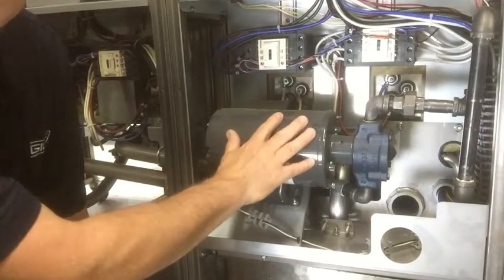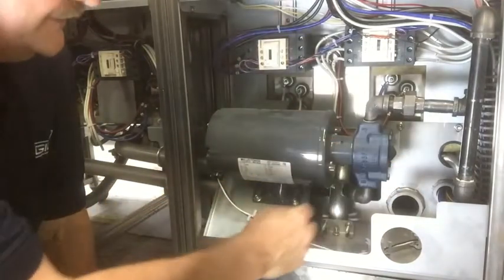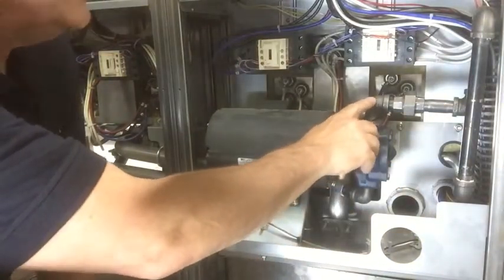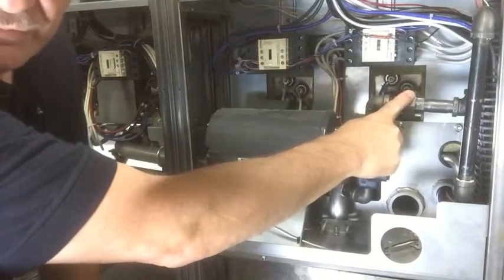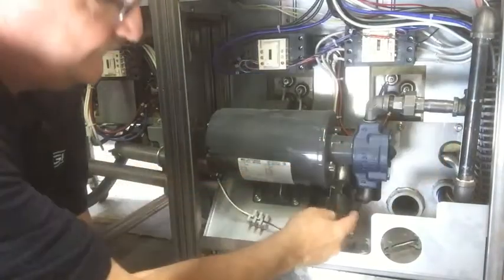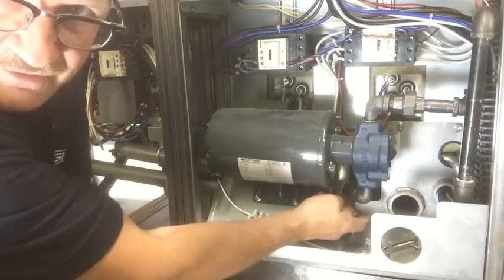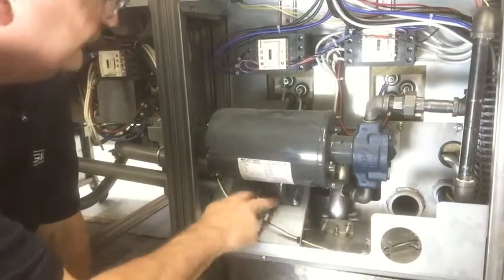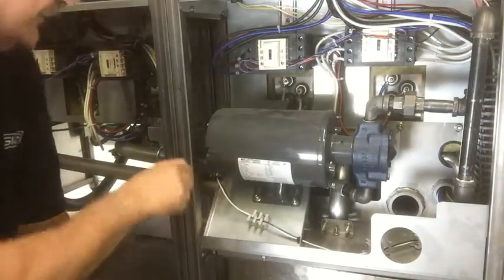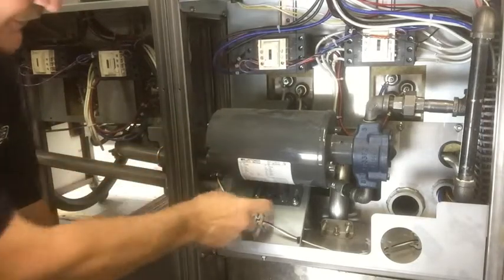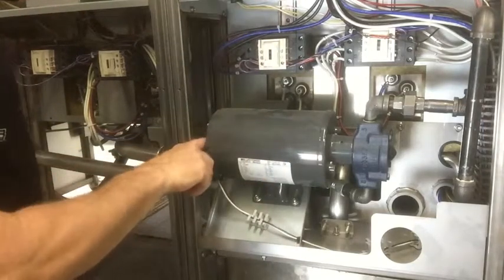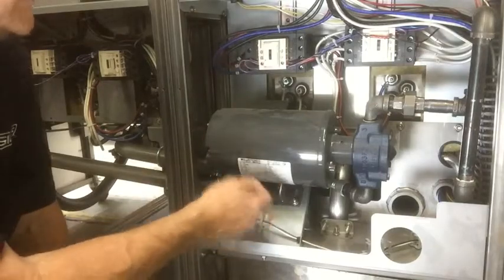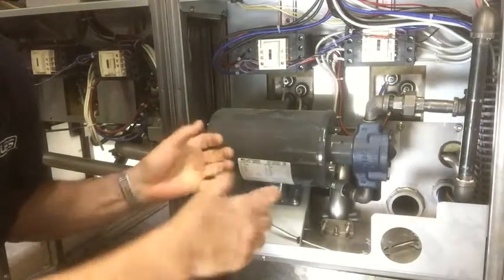Filter pump, it's motor, pump. Filter pump removal is as easy as breaking this union, taking this pipe loose, taking this hose connection loose right here, and then you've got 4 bolts. Unwire the motor from the end bell right here. Once you get these loose, it'll turn around. You can unwire these leads and remove the pump, put the new one back on, and reverse everything.